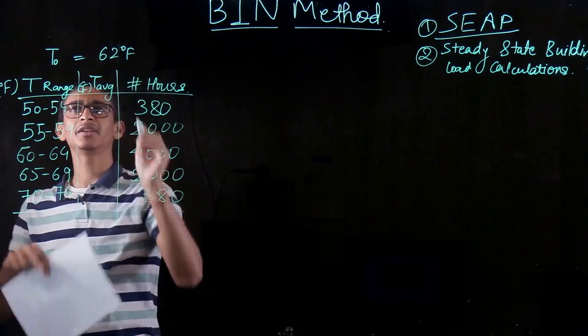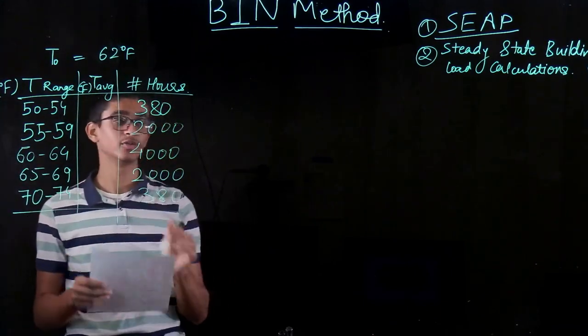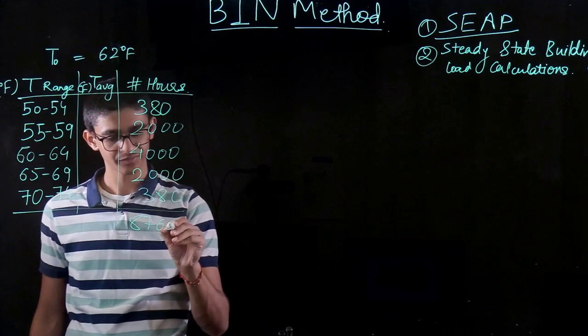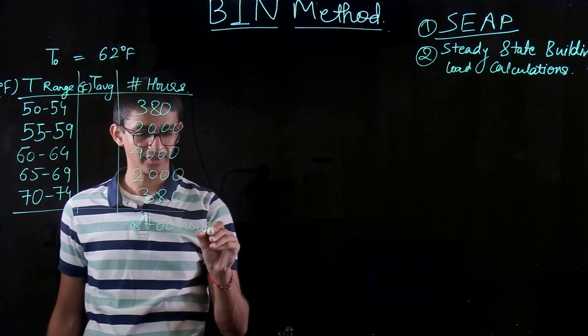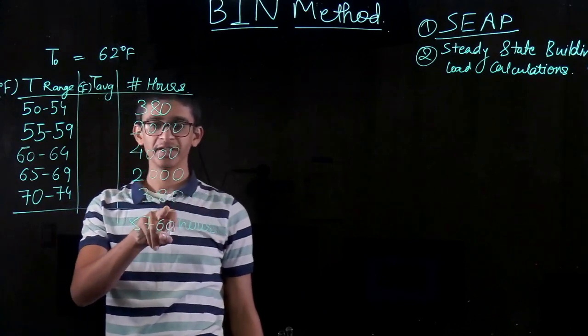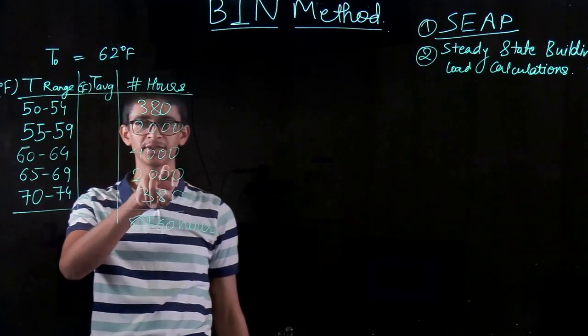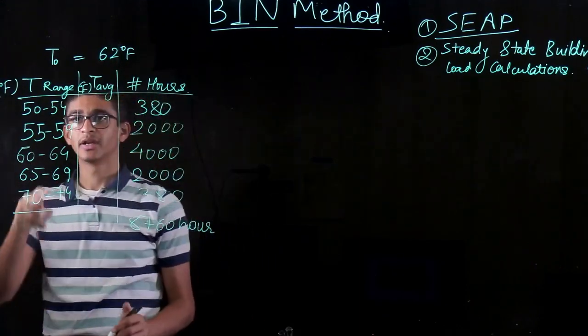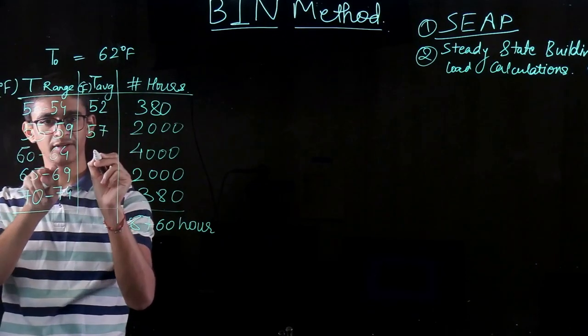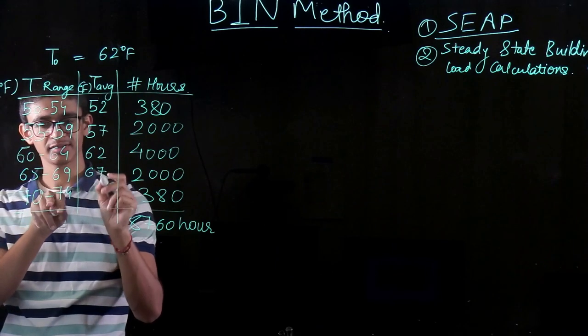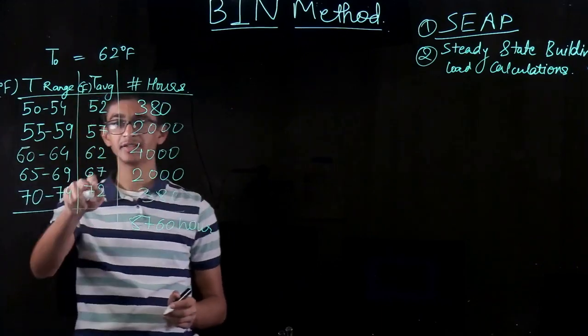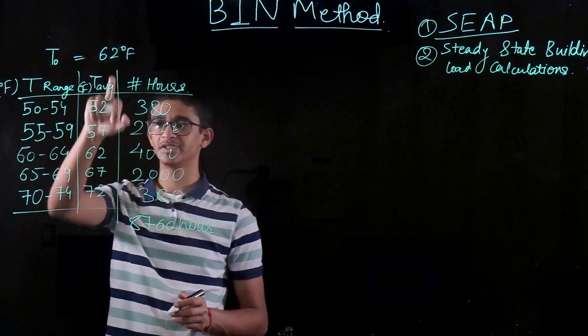The average outside temperature is 62°F. These hours sum up to 8,760, which is the total number of hours in a year. The average temperature for each bin is: 52°F for the first bin, 57°F for the second, 62°F for the third, 67°F for the fourth, and 72°F for the fifth. I've split the hours in such a way that the weighted average temperature still comes out to 62°F. Now the idea is we do more calculations — one per bin — instead of just one for the whole year.